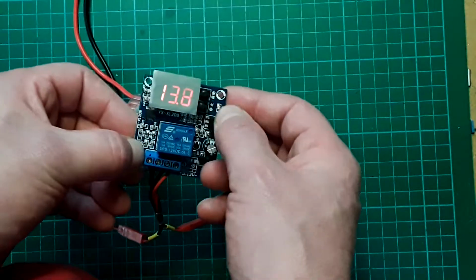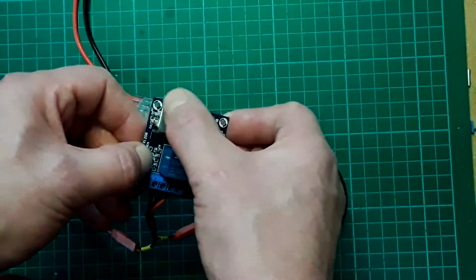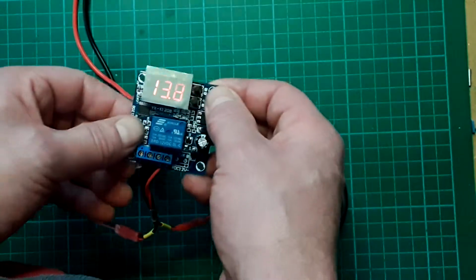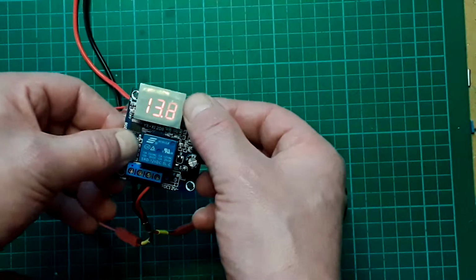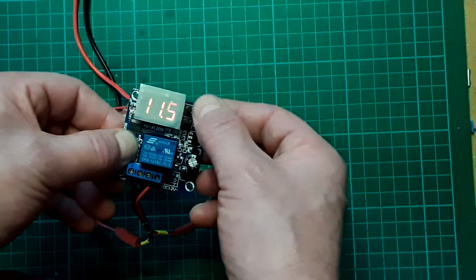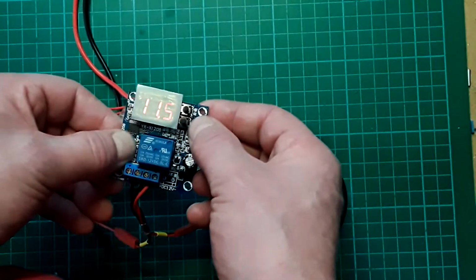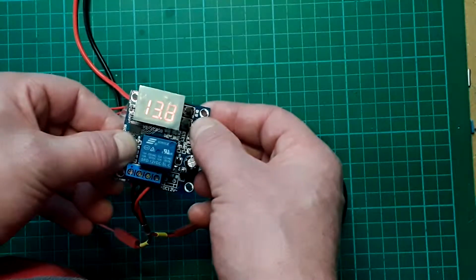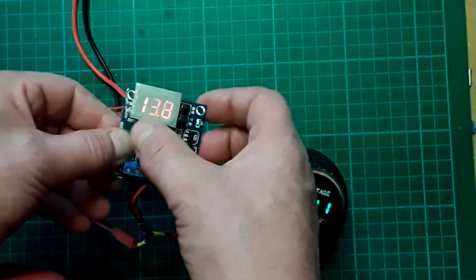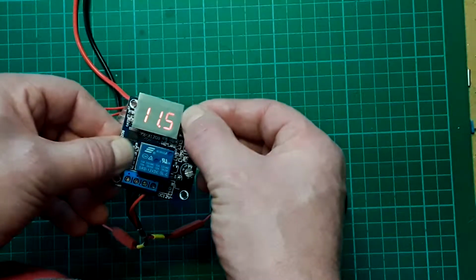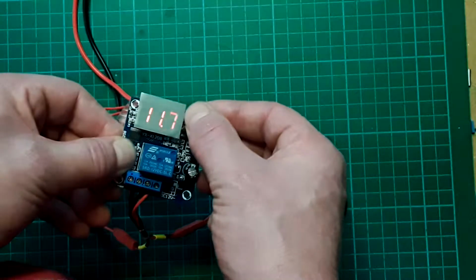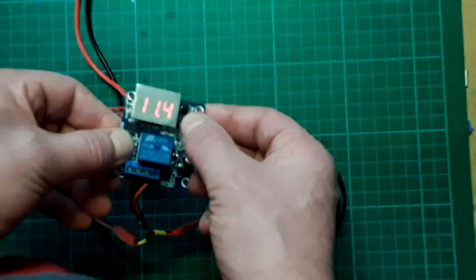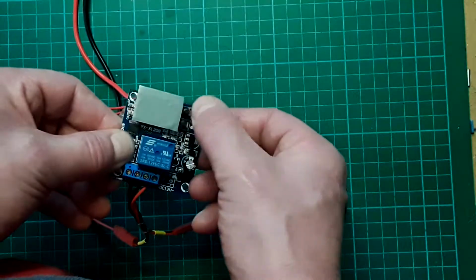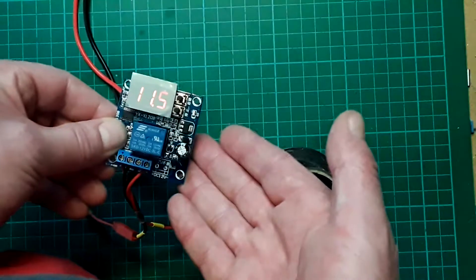So to set it up, by default it's showing 13.8 volts, which is a nominal voltage for a 12-volt battery. The top one shows the lower threshold, set at 11.5 volts - that's as low as I'd want a 12-volt battery to go. Then it defaults back to reading the voltage. If you want to change that lower threshold, press and hold, and it increments - top one increments, bottom one decrements. So we'll take that back to 11.5 volts. To set it, there's no enter, you just let it time out.